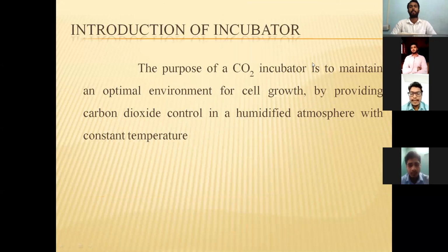Carbon dioxide incubator is also known as a gas incubator. An atmosphere is created that is as natural as possible to develop the cell culture. This carbon dioxide incubator maintains the optimum environment for tissue culture cell growth by providing carbon dioxide inside the incubator and controlling a humidified atmosphere with constant temperature, that is 37 degrees Celsius. The temperature and carbon dioxide must match the cell as precisely as possible.